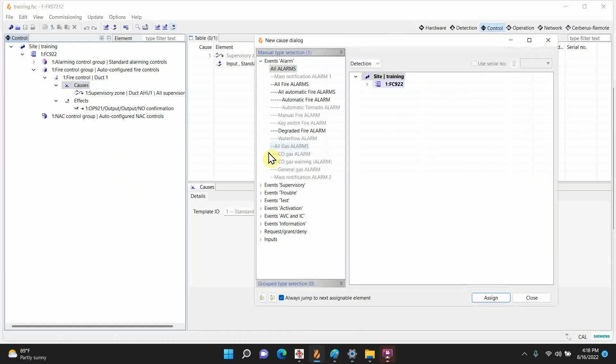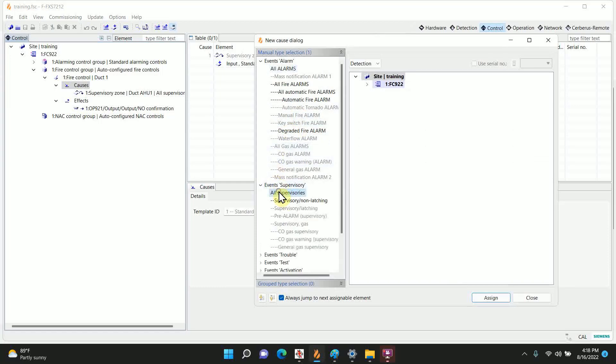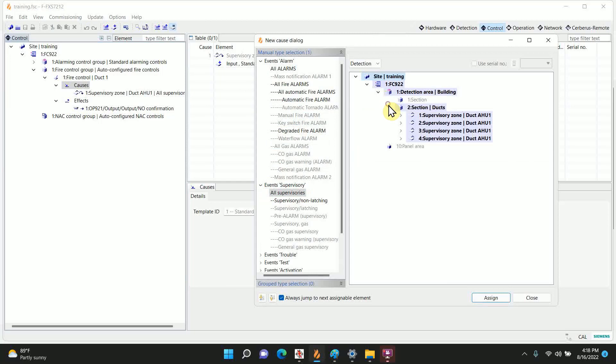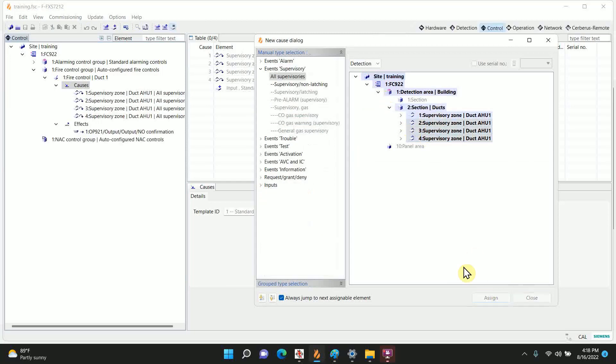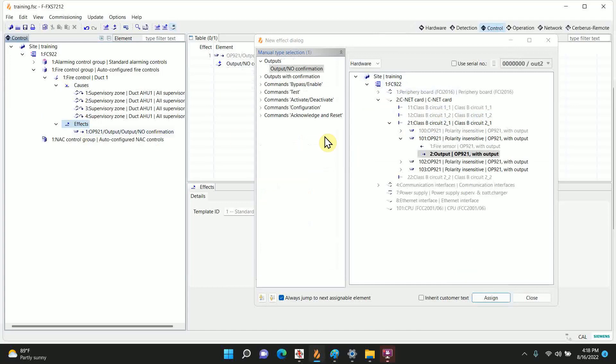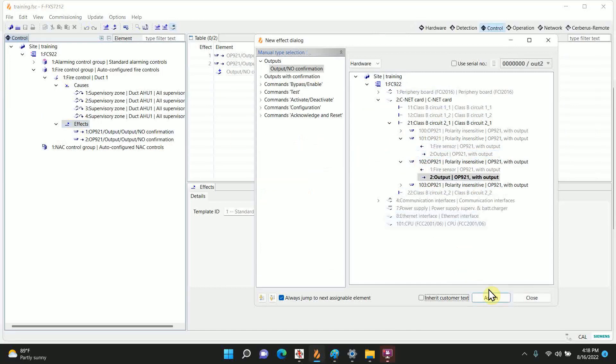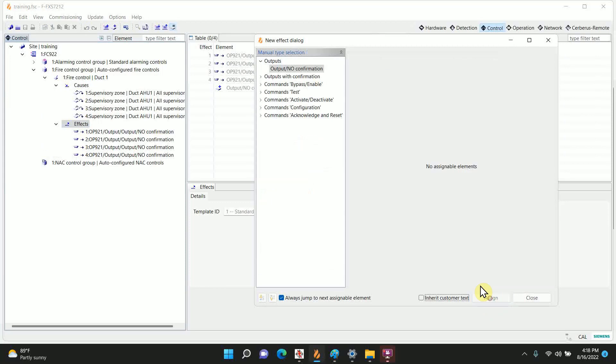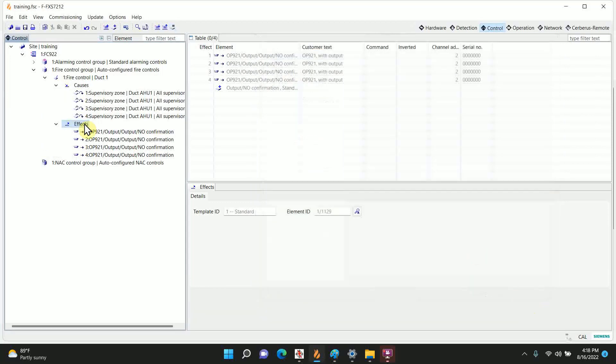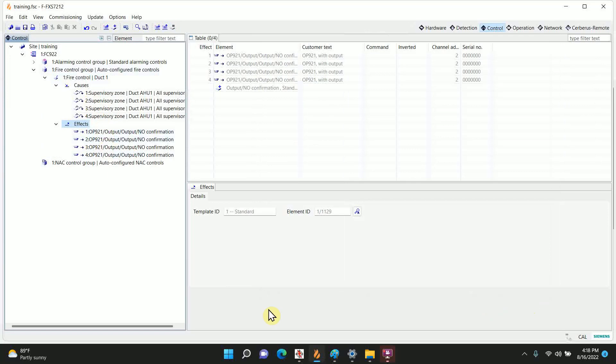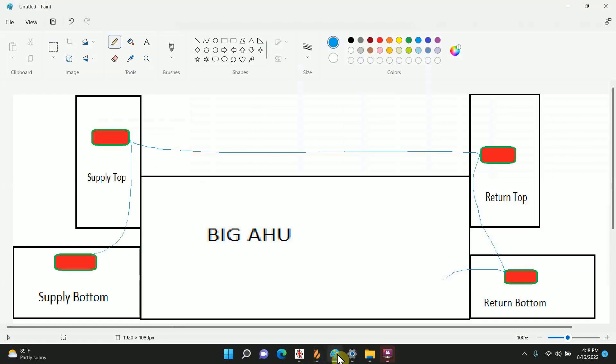By default it's going to be an OR effect, so any one of these will trigger it. Again I'm going to go to supervisory, all supervisories, and we're going to click on the other three. Assign, effects, we're going to assign these other effects, and close. So now look in our control, it has four different things that can cause this. Being an OR does not require two or more to activate, just a single one. And the effects, all four of our duct detectors will have the relay trip.